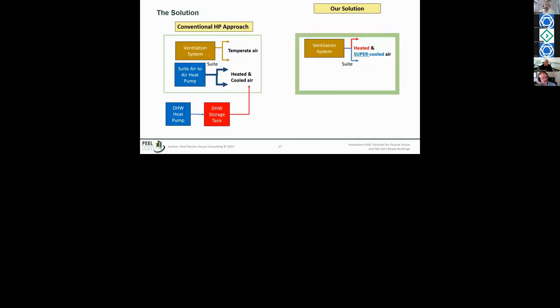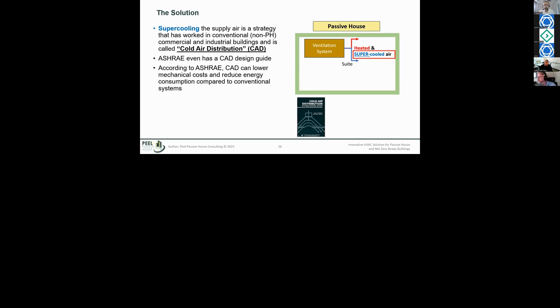Next slide, please. What we're proposing is a strategy called supercooling, or cold air distribution, an industry term. This is a strategy or technology already implemented in commercial and industrial buildings. Essentially, the air we supply into the building is supercooled—dropped to a much lower temperature than conventional, instead of the regular temperature you'd get off an air conditioner, heat pump, or chiller.